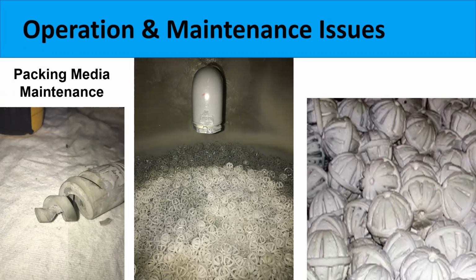Some of the common things we see crop up in maintenance issues often start in the recirculation of the wet pack bed system. So in this particular case, you have the packing media that's just randomly dumped inside the pack vessel, and you can see a pigtail nozzle on the left. We often use different types of nozzles. Most all are open cone type to provide good coverage. But here you have a situation where there's not enough packing depth that was provided, maybe due to settling from shipping or whatever.